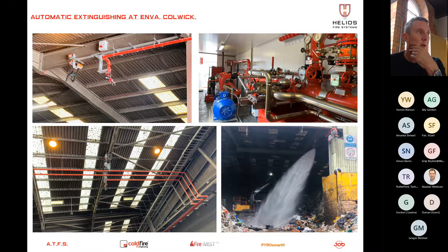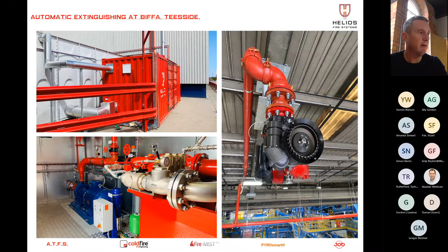This is Biffa at Teesside, at their PRF. In this case the client only wanted one pump - we design each system to the client's requirements, whatever their insurer wants, whether that's one pump, two pumps, or diesel generator backup, we can supply it. Our cannon system can alternate the flow - no other cannon system on the market can do this. We can send it from 500 liters to 3,000 liters a minute through the same cannon, simply by alternating the regulator to give us the flow required for that particular area.